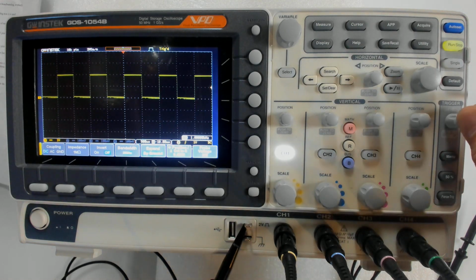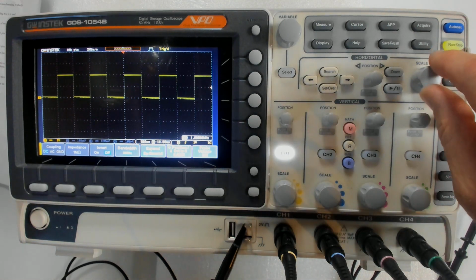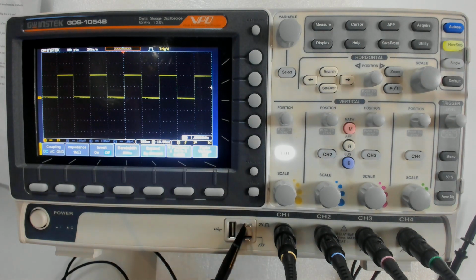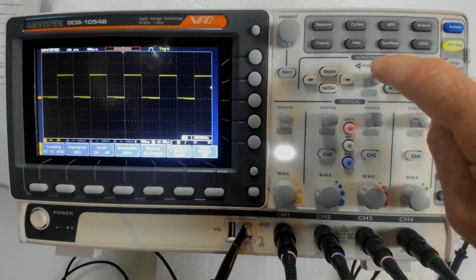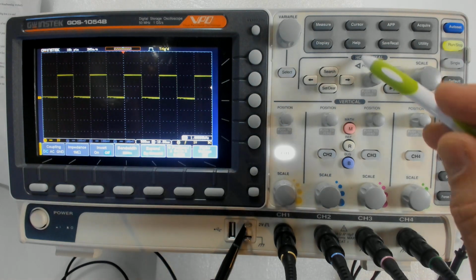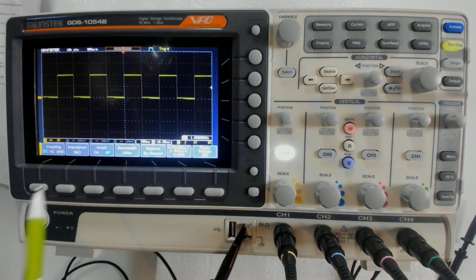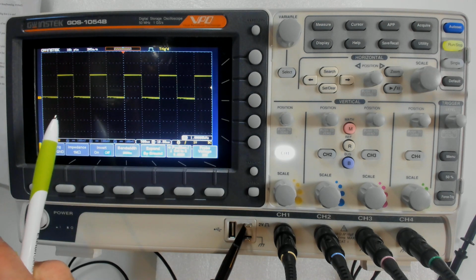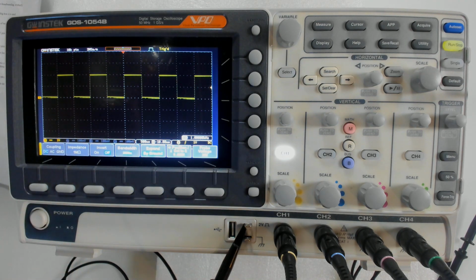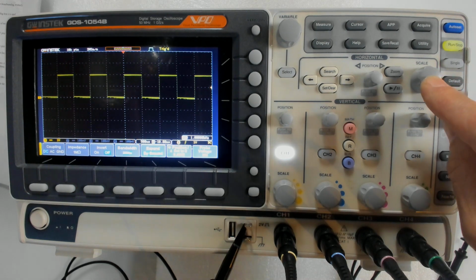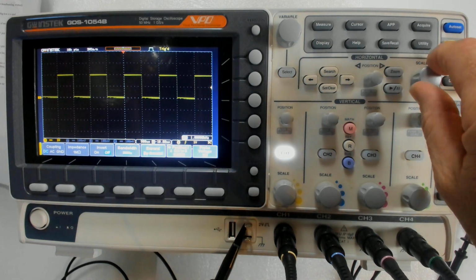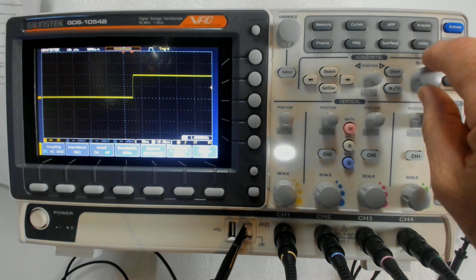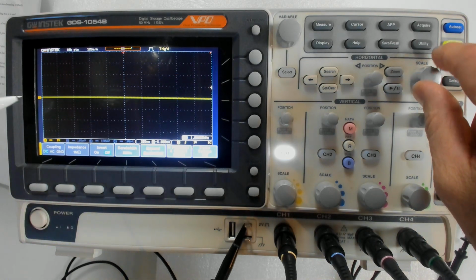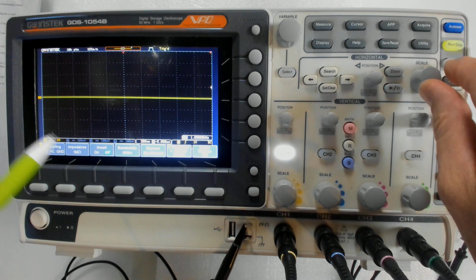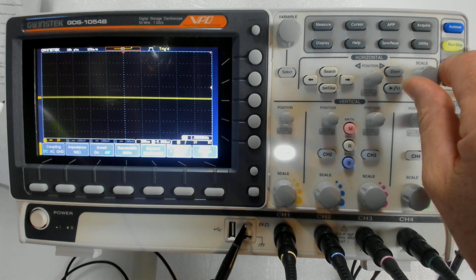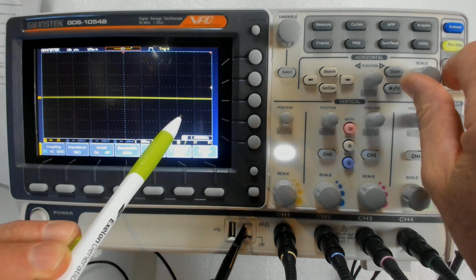Let's assume you had a trigger level in there, but you might see something where you're scanning too fast or too slow. Let's show you what that looks like. That has to do with the horizontal scale, which is really telling you how many seconds each square is worth. So I can use this scale knob to sweep across the screen faster or slower. Now I'm scanning really fast, and look, I don't see anything, but it's because I'm zipping across the screen so fast that I'm only seeing a very little piece of the waveform.